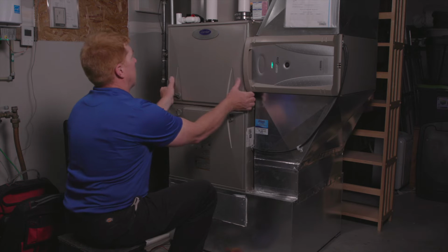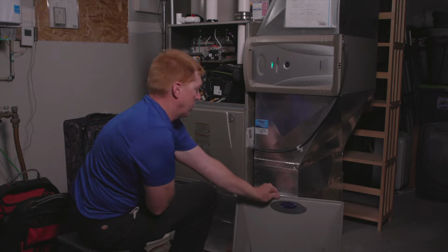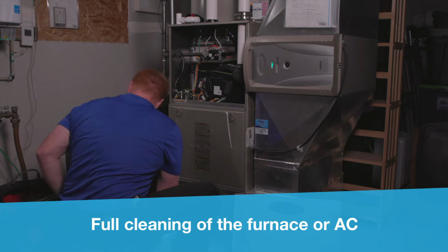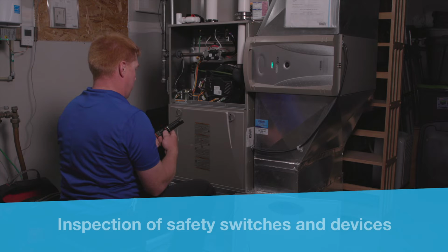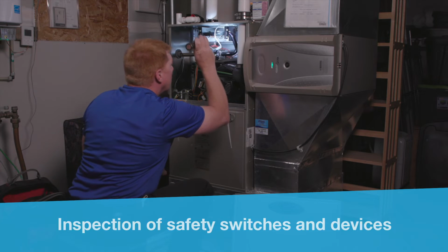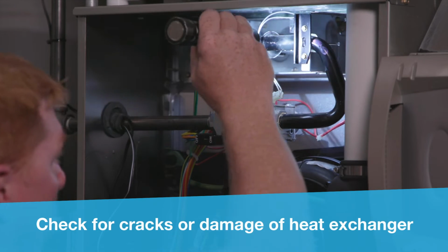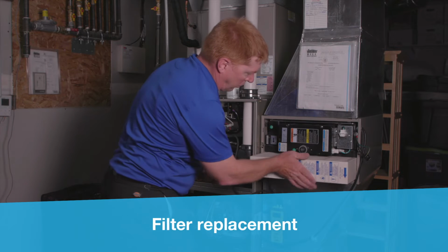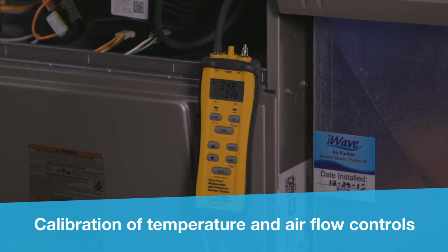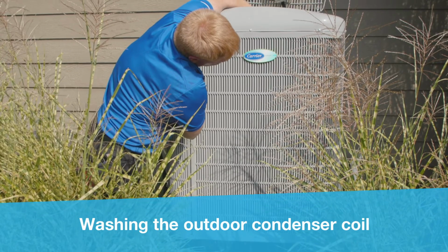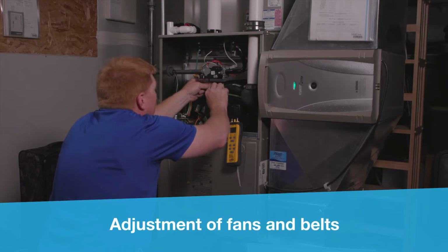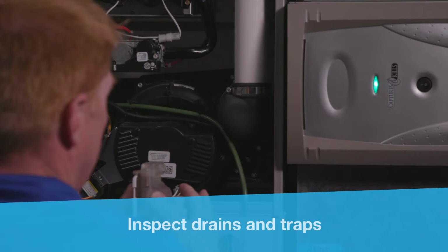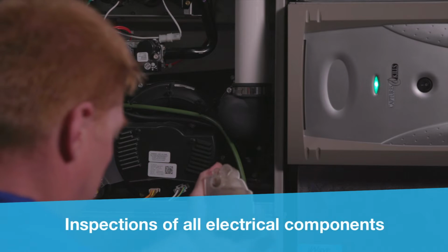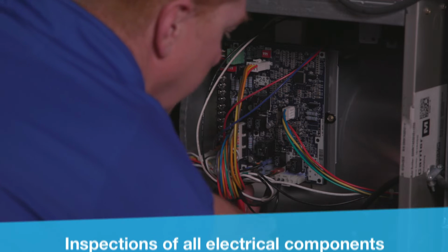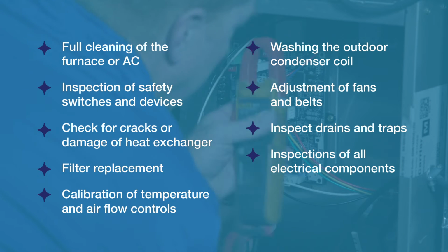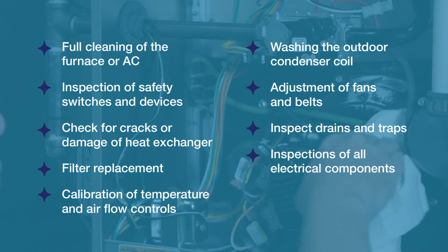Annual furnace and AC maintenance performed by a trained technician should include full cleaning of the furnace or AC, inspection of safety switches and devices, checking for cracks or damage to the heat exchanger, filter replacement, calibration of temperature and airflow controls, washing the outdoor condenser coil, adjustment of fans and belts, inspection of drains and traps, and inspection of all electrical components.